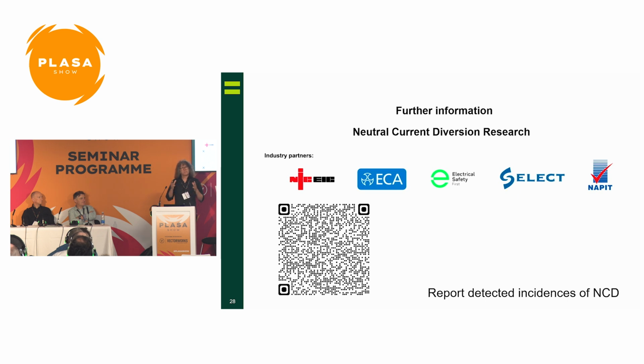IET's got some guidance out on this in Guidance Note 3. But before you do anything on site, before you take a measurement of Ze, for example, where the measurement of Ze is taken by disconnecting the earthing conductor, you're meant to check for neutral current diversion. So if there are currents in the order of amps flowing through the earthing conductor or through the bonding, we want you to inform us about that problem. And this is the way to do it.